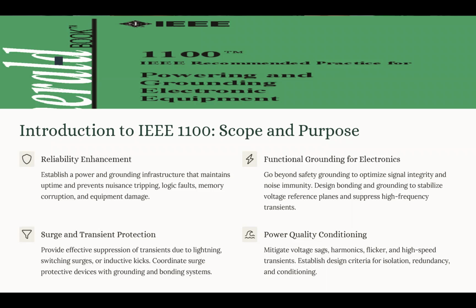The traditional grounding methods are normally safety focused. Okay, so it's designed to prevent electric shock or fire. However, there are some sensitive electronics like computers, medical equipment, or telecom systems that need a functional grounding approach. Okay, so that approach prioritizes signal integrity, low noise reference planes, and transient suppression instead of just safety focus.